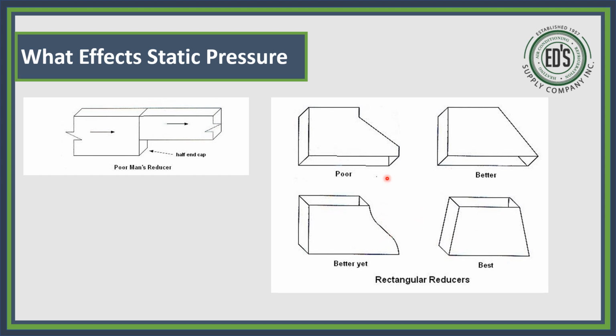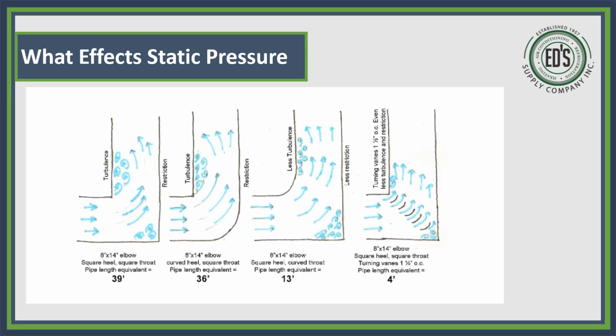Also, on your transitions, a center taper transition is always best. Keep in mind, I've seen this, but in a worse way, where this line here went all the way down to here, and the air was coming out of the unit right here, hitting this and bouncing back. Huge static pressure issue, caused the compressor to almost fail. If he would have had this in here, would never have had any problem.